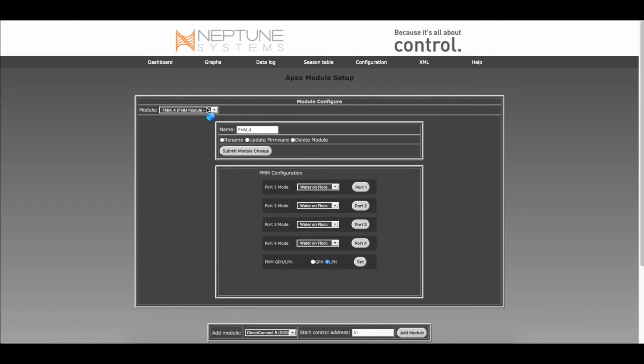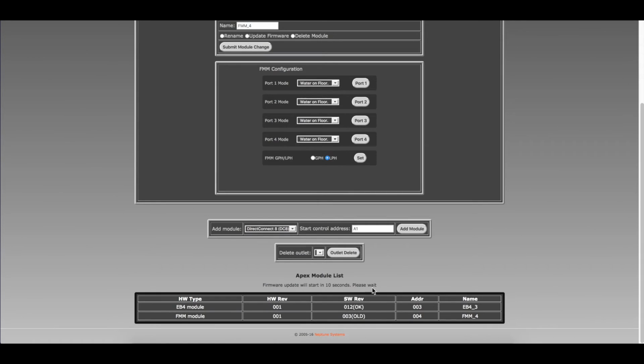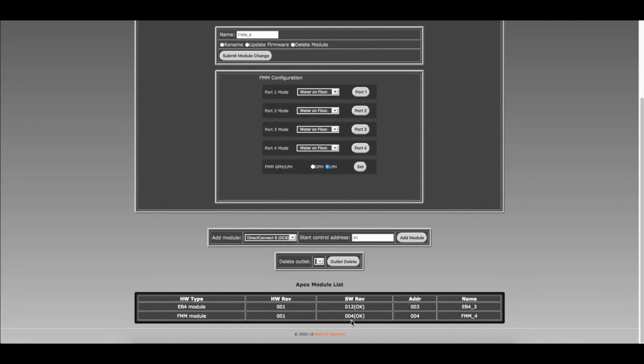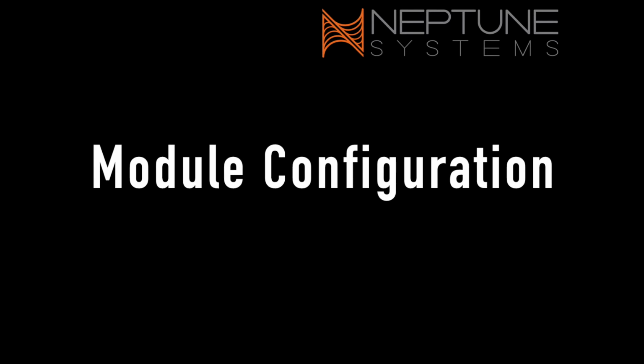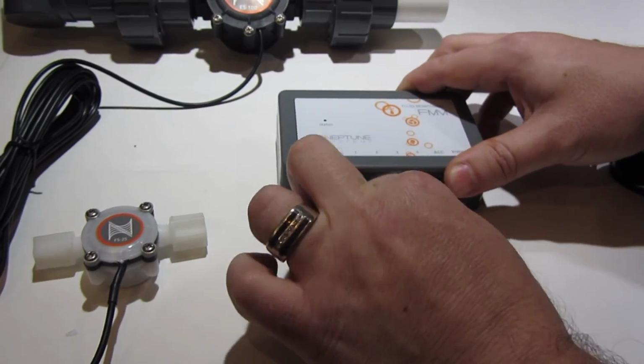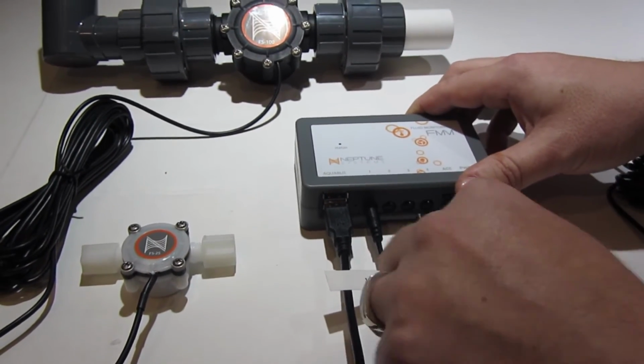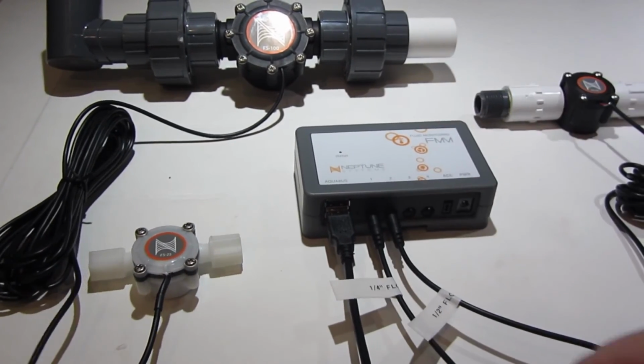Make sure that the modules that you want to update are now being displayed in the center of the screen. Select the Update Firmware, then click on Submit Module Change. You'll notice below the progress of the module update. Now the FMM module firmware should show OK. Now that we have updated the module, we can plug in each of the sensors into their individual ports.